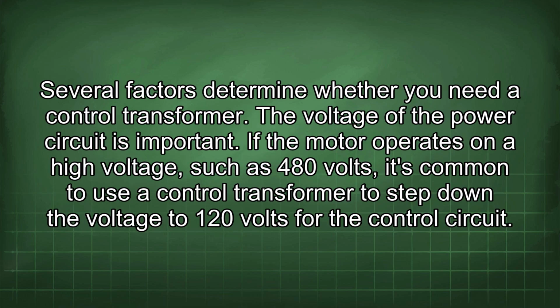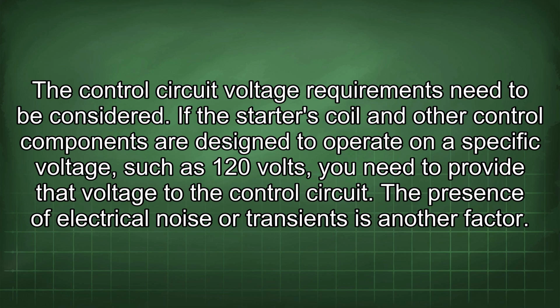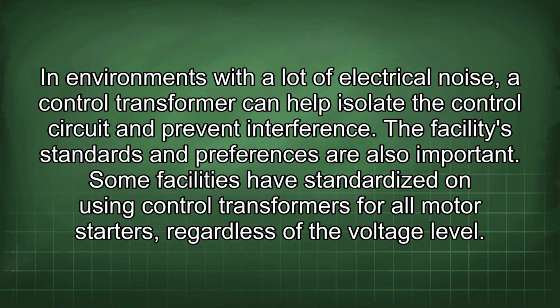Several factors determine whether you need a control transformer. The voltage of the power circuit is important. If the motor operates on a high voltage, such as 480 volts, it's common to use a control transformer to step down the voltage to 120 volts for the control circuit. The control circuit voltage requirements need to be considered. If the starter's coil and other control components are designed to operate on a specific voltage, such as 120 volts, you need to provide that voltage to the control circuit. The presence of electrical noise or transients is another factor. In environments with a lot of electrical noise, a control transformer can help isolate the control circuit and prevent interference. The facility standards and preferences are also important.